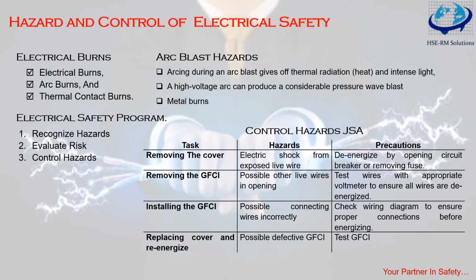Arc blast occurs when a powerful high amperage current or arc is released in a distribution box or a motor control center. That's a confined flash. An arc in an open space, with the energy escaping in 360 degrees in all directions, is called an open flash. Now what is thermal burn? Thermal burns occur when electricity starts a fire or explosion. Clothing may catch fire and thermal burns may result from the heat of the fire. An extremely high energy arc can also damage equipment, causing fragmented metal to fly in all directions.